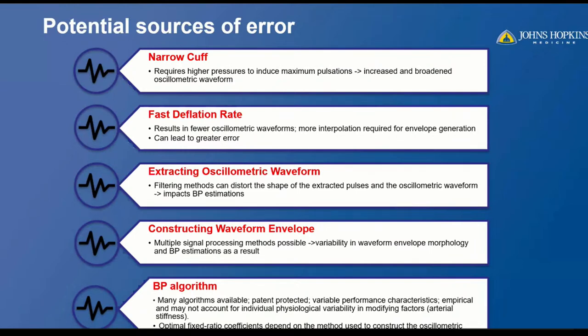One difference I didn't highlight earlier is the cuff. Blood pressure cuffs used with manual auscultation are required to conform to certain dimensions: the inflatable portion needs a width that is at least 37 to 50% of the measured midarm circumference of the patient, and a length that's 80 to 100% of that circumference. Cuffs used with automated devices don't have such requirements, because manufacturers are allowed to innovate and develop cuffs appropriate for their device system.